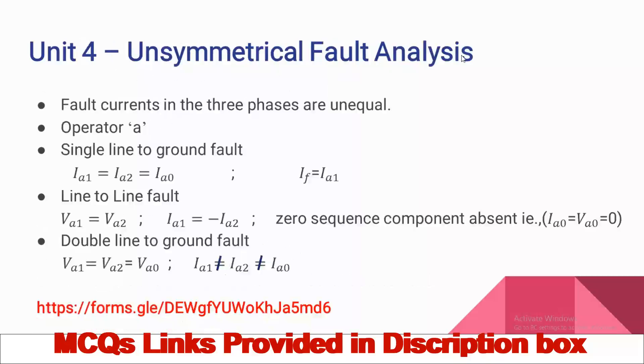Unit Four: Unsymmetrical fault analysis. An unsymmetrical fault means fault current in the three phases are unequal, so calculation is required for each phase separately. Using the symmetrical components method, operator 'a' denotes a phasor rotated in the anti-clockwise direction. For a single line-to-ground fault — the most frequently occurring fault at about seventy percent — the condition is that all sequence currents are equal: positive sequence equals negative sequence equals zero sequence current. The fault current is I-f equals 3 times I-a1 (any sequence current multiplied by three).